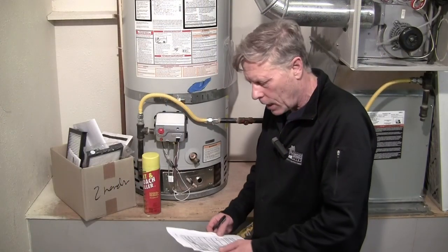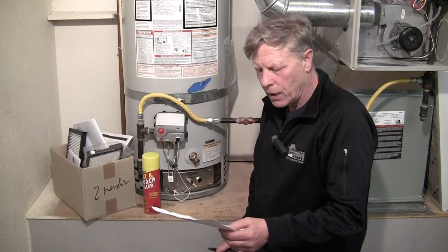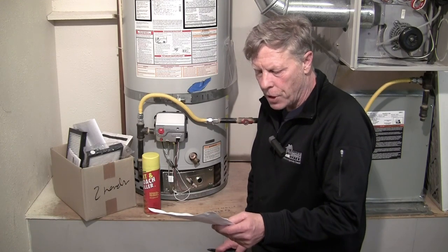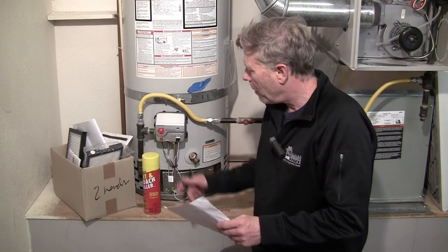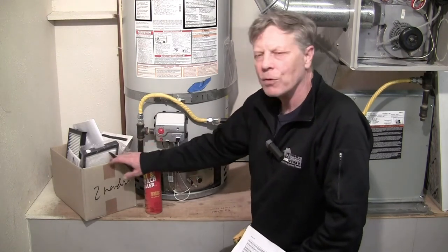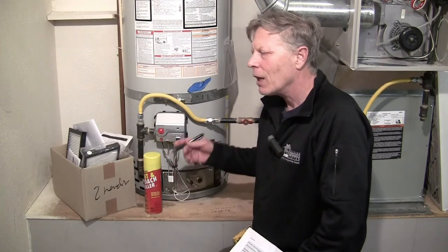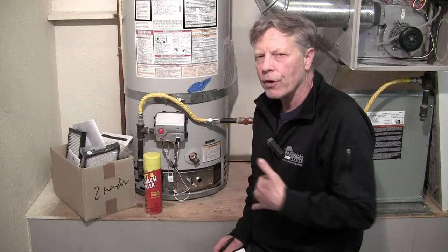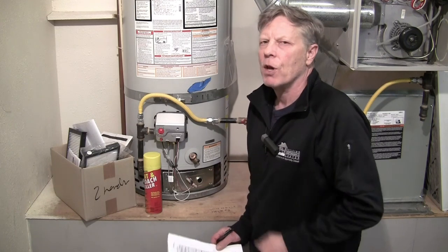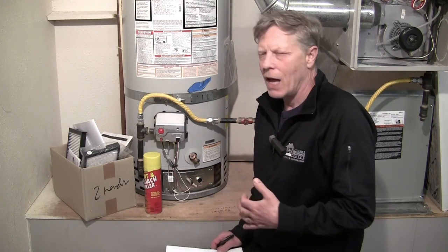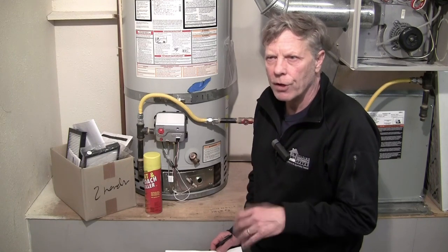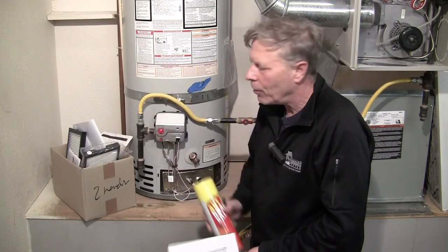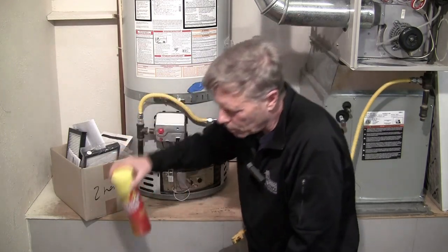Alright, we're here on line 4. We're going to do our visual inspection of the CAZ for unsafe conditions. On the form it says, is it free of flammable products and combustibles? I put some flammable products and some combustibles here just to make a point. A lot of times in water heater closets or in garages, wherever furnaces and water heaters are, occasionally that becomes a storage area. And we just don't want to have anything close to the water heater or furnace because they could light on fire. This is a pressurized vapor that's flammable. A thing of gasoline could do it too.